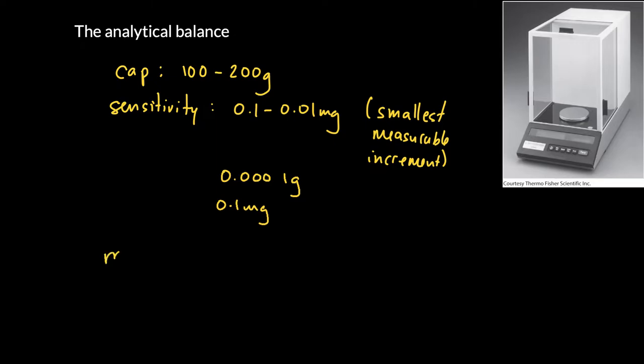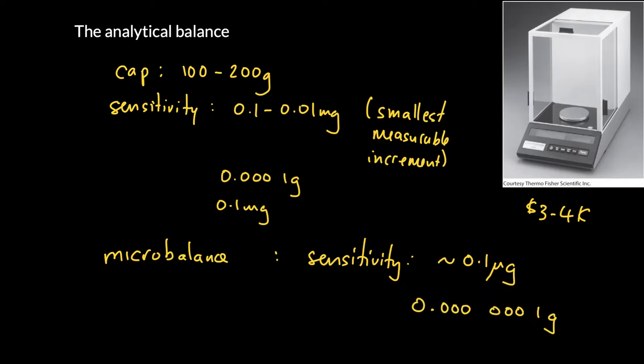You can also use a microbalance. The microbalance is going to be a couple of orders of magnitude more expensive than an analytical balance. So an analytical balance might run you $3,000 to $4,000. A microbalance might start running you $10,000 to $100,000, and its sensitivity is much smaller, somewhere in the order of maybe a tenth of a microgram.